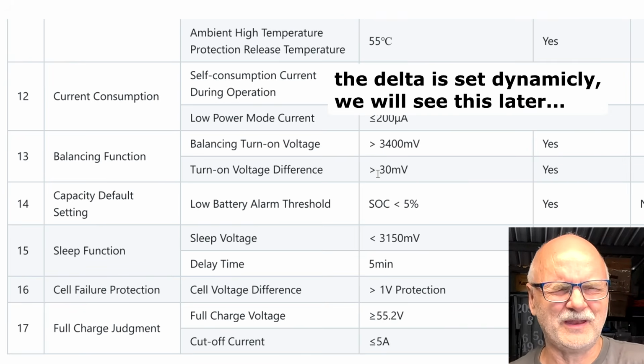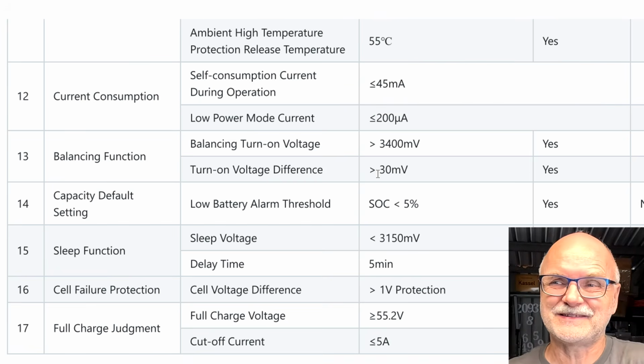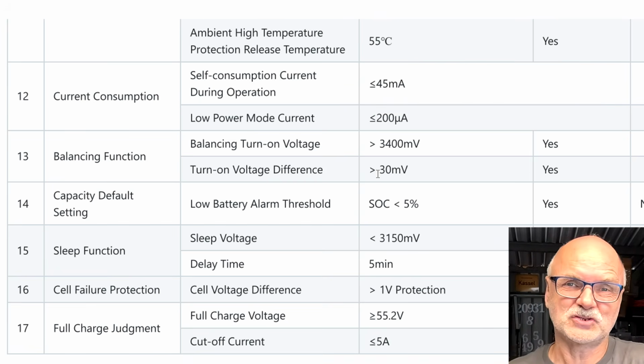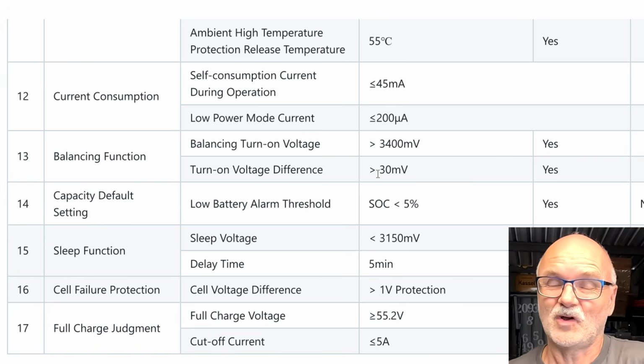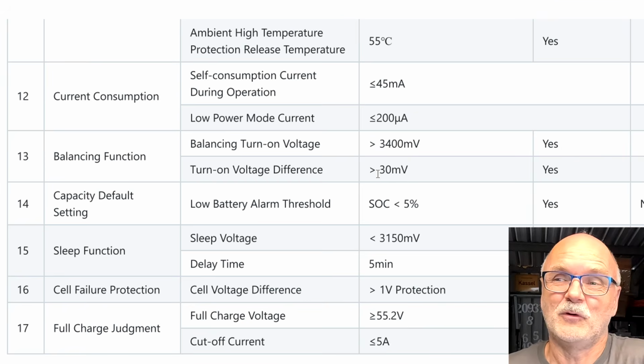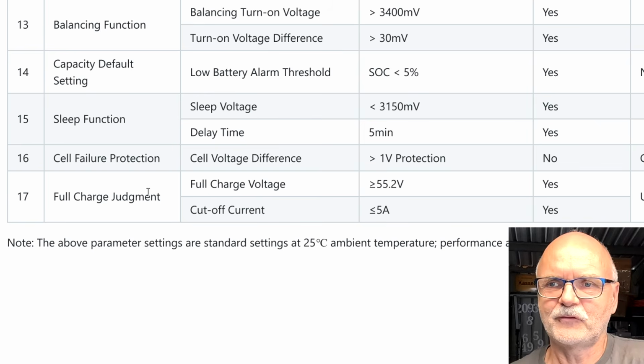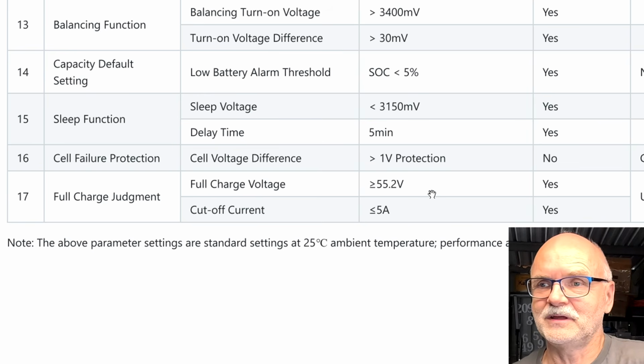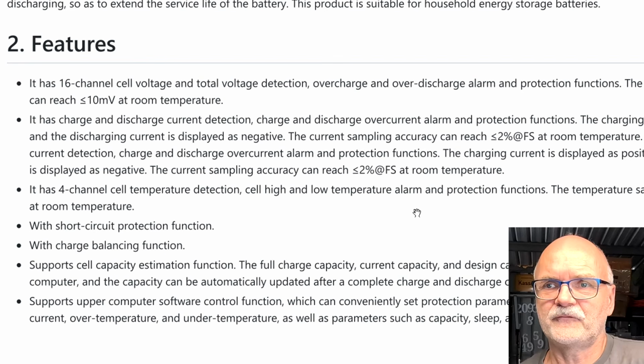And I think the difference can be dialed down to only 20 or even 30 millivolt. And Gobel Power told me it doesn't make really sense to go lower because the voltage measurement accuracy at this point is not very high anyway. So balancing down to 10 or even 5 millivolt wouldn't make sense. We've got a full charge judgment if the battery voltage is over 55.2 volts and the current is lower than 5 amps. So features, so 16S battery.